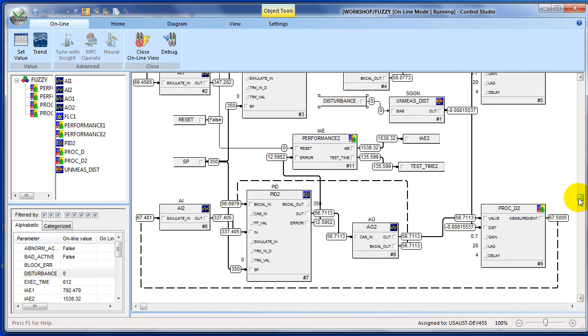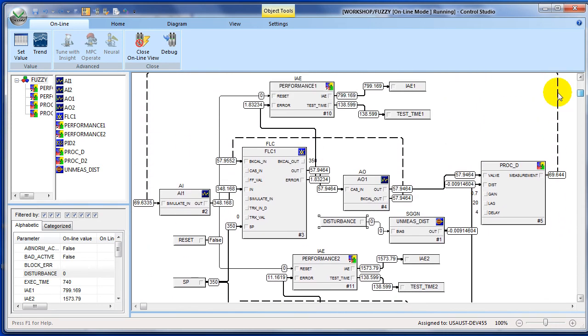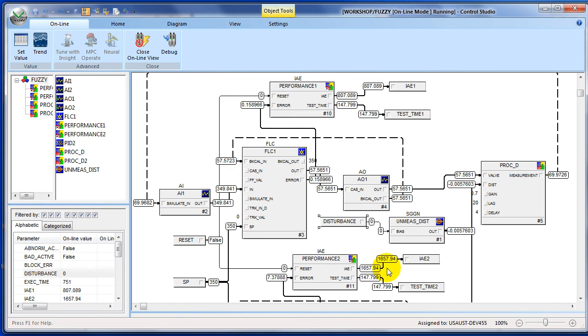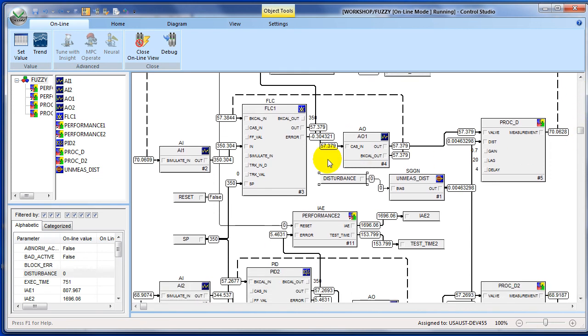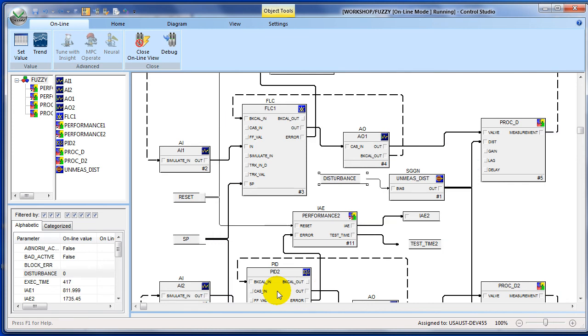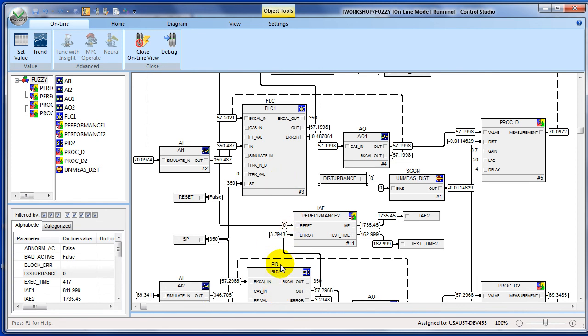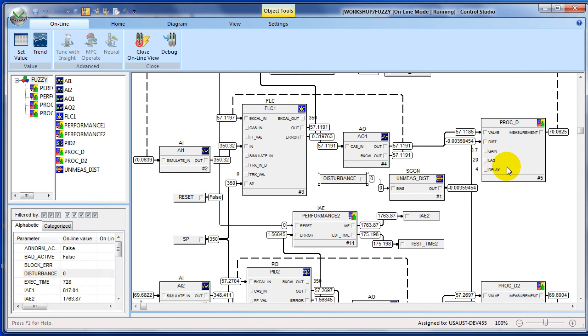I hope this demonstration has been helpful in showing how fuzzy logic control can be used to improve performance. If you have a lag-dominated process characterized by a number of unmeasured disturbances, you can expect a fairly dramatic improvement in performance. Fuzzy logic implemented as a function block that runs in a module within your controller means that it behaves in an identical way to your PID control — so you can essentially substitute it for PID control in processes that would benefit from it. I hope this workshop has been helpful in understanding how fuzzy logic control can be applied to improve control.